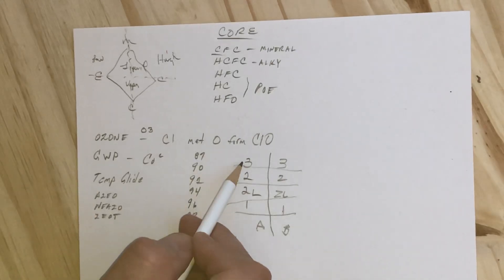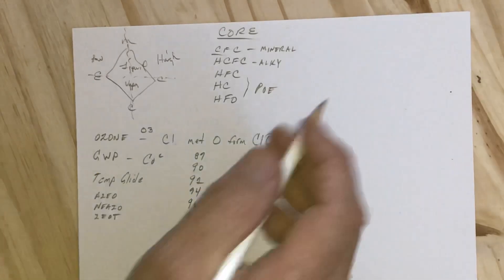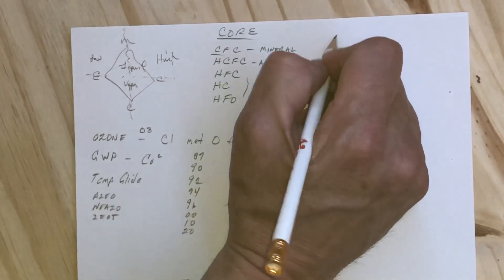If you have a B1 refrigerant like 123, that's not flammable at all but has some toxicity, all the way up to the hydrocarbon R-600 refrigerant, which is not very toxic but highly flammable. Then you have some newer ones like 1234yf that are 2L - they have slight flammability but are not toxic.